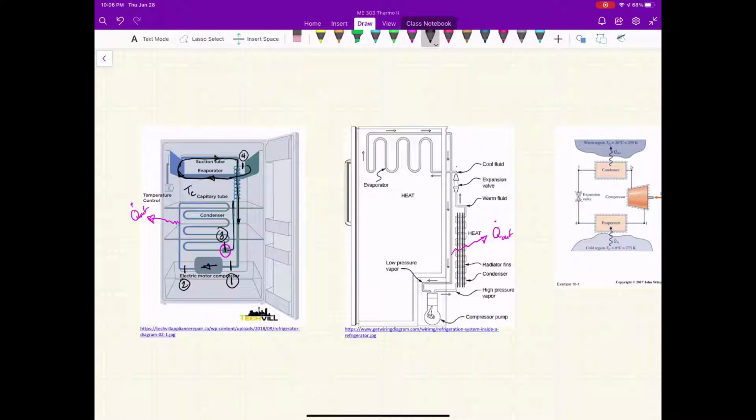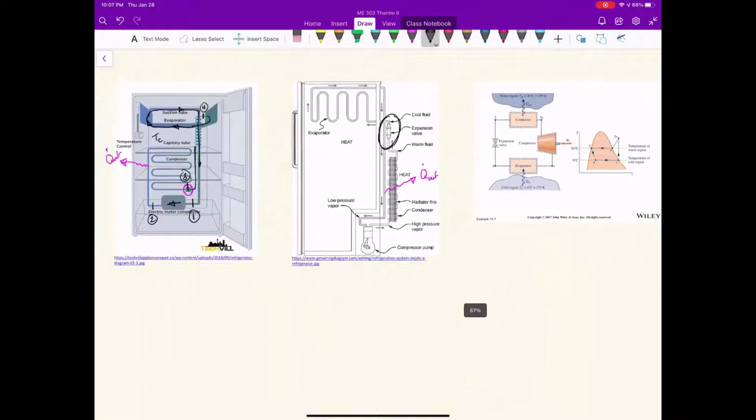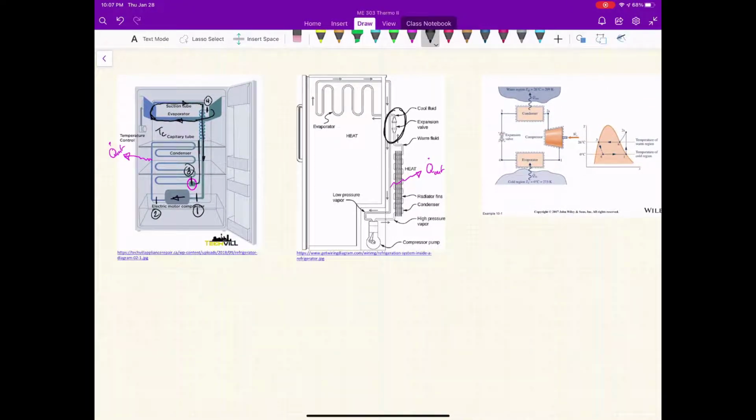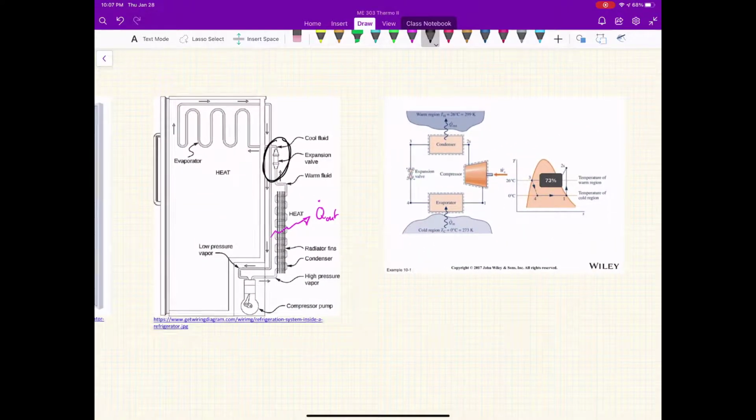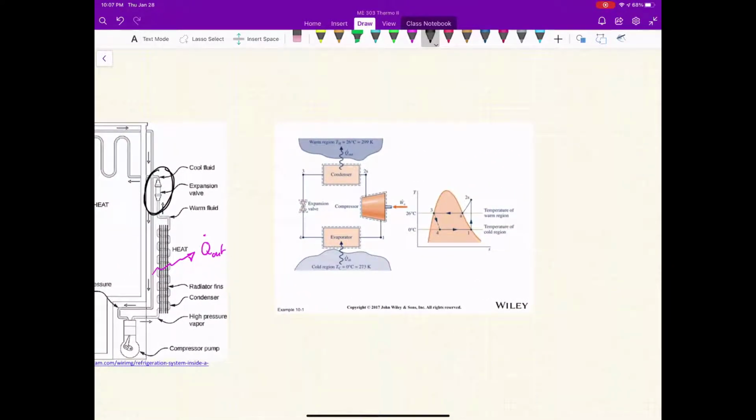to drop the temperature of the capillary tube even more. Okay, and this is in contrast to this second diagram, where instead of having the capillary tube, there's an expansion valve or a throttling valve or a plug, if you will. It does the same thing as the capillary tube. It just does it in a much more reduced volume. And obviously you can't weave it around the return tube of the evaporator section, so you can't dump heat from the evaporator tube, the return evaporator tube, quite as easily. So let's take a look at this on the TS diagram.